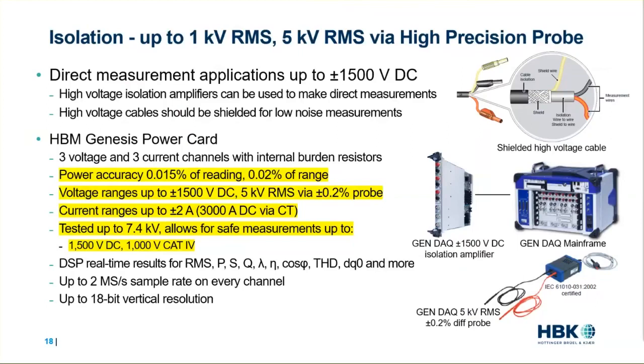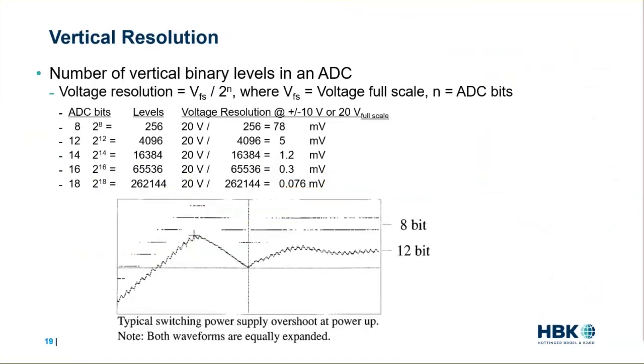Now, every voltage and current channel is sampled at 2 million samples every second, and it has up to 18 bits of vertical resolution. Speaking of vertical resolution, here's a slide that clearly shows the importance of high vertical resolution. This diagram is the result of an experiment I did many years ago, acquiring the overshoot of a switching power supply at power up. I used a measurement system that had both an 8-bit and a 12-bit digitizer in the same system. So I acquired the data at the same sample rate and equally expanded both waveforms.